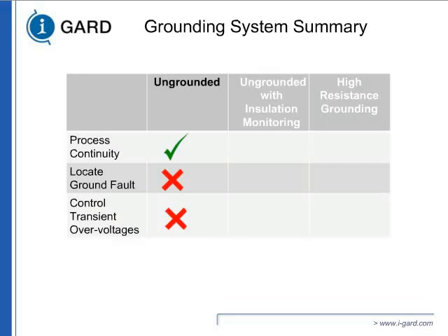We could not locate the ground fault. We could not control the transient overvoltage. The only way to locate the ground fault, as far as we knew at that time on a delta system, was to keep on shutting circuits down one by one. With Murphy's law, the fault is always going to be on the last circuit you shut down. So basically you had to do all of them.